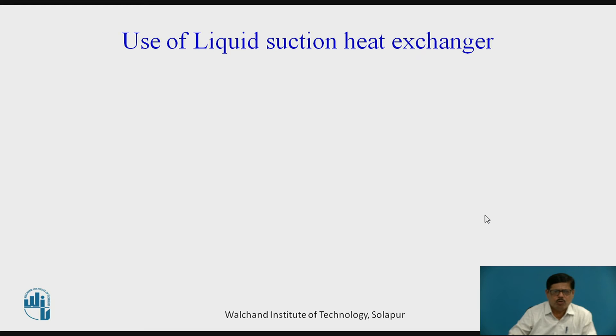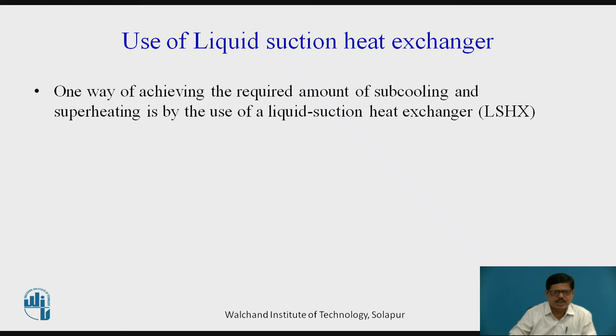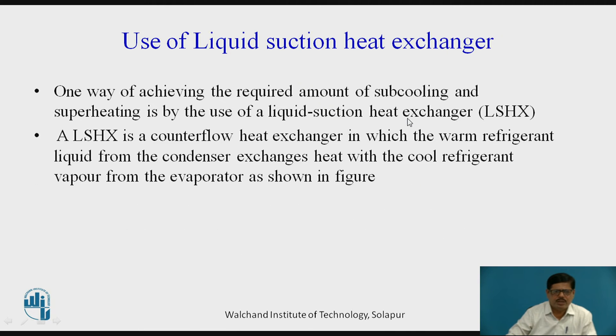So, how can we achieve superheating while increasing the refrigerating effect? One way of achieving the required amount of subcooling and superheating is by use of a liquid suction heat exchanger. It is a counterflow heat exchanger in which warm refrigerant liquid from the condenser exchanges heat with cool refrigerant vapor from the evaporator, as shown in the figure.